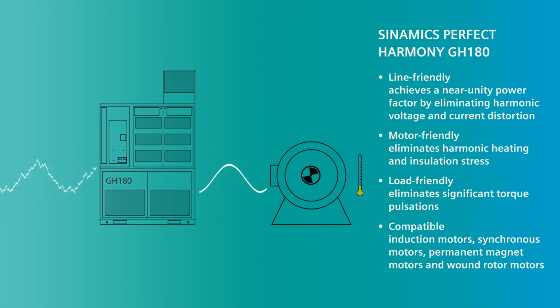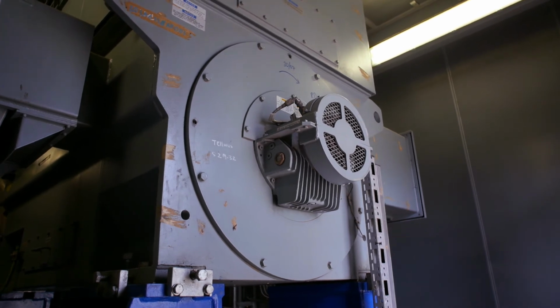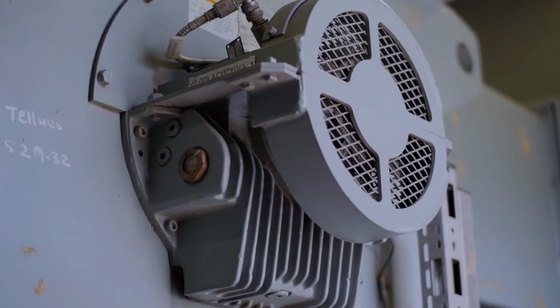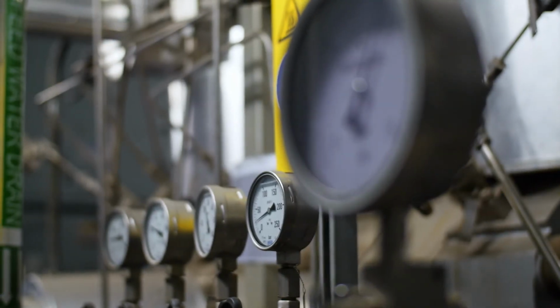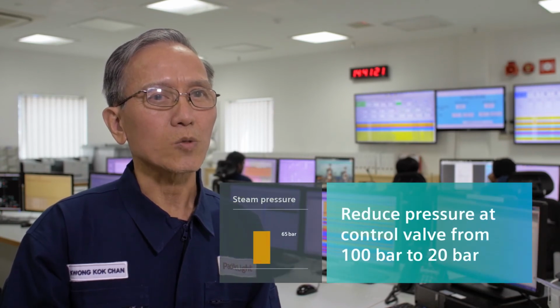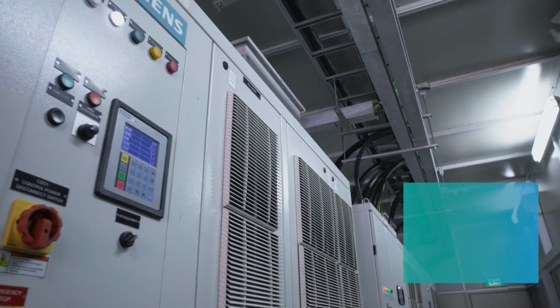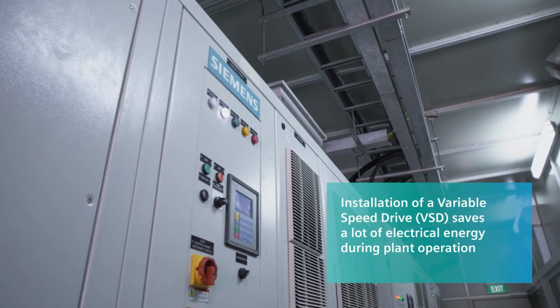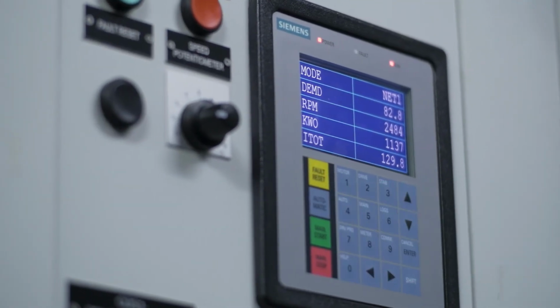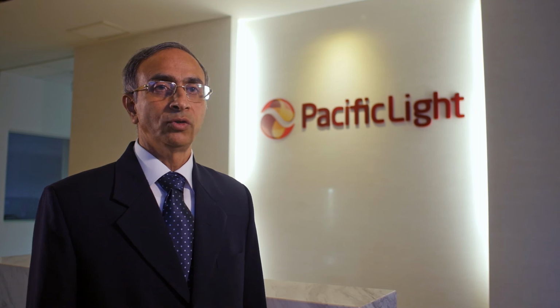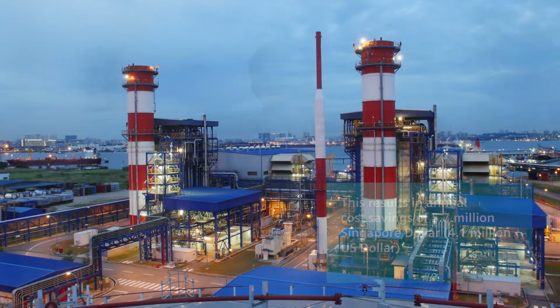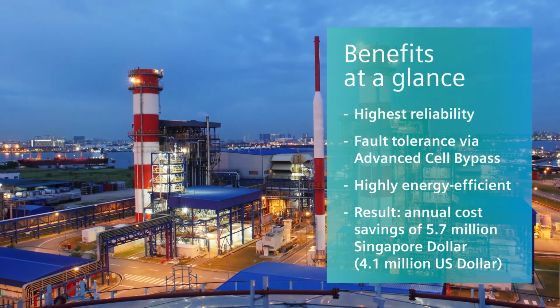rotor motors. The installation of this VSD project controlled the speed of the pump and moderated the discharge pressure optimally according to the load profile, delivering the required flow at a much lower motor power. The pressure difference across the throttle control valve has now been reduced from 100 bar to 20 bar. It has also reduced auxiliary power consumption of the feed water pump, thereby improving the generation output and efficiency of our unit. We completed a modification to our plant in 2014, which has led to annual cost savings of $5.7 million. Pacific Light's power plant stands as one of the most efficient operating units in the Singapore power market today.